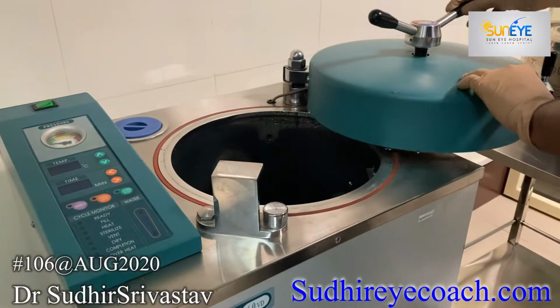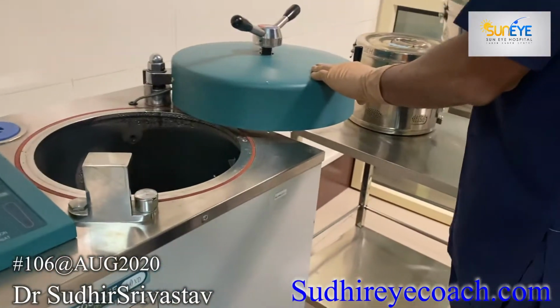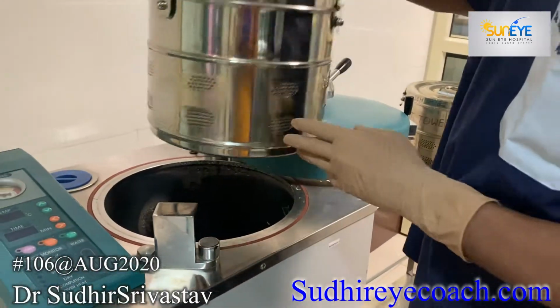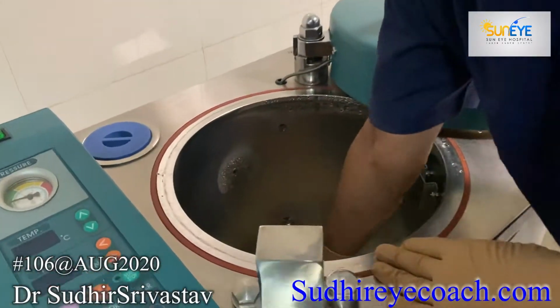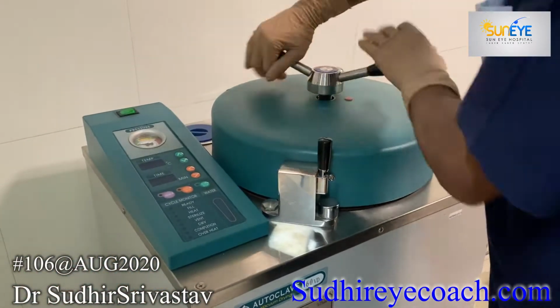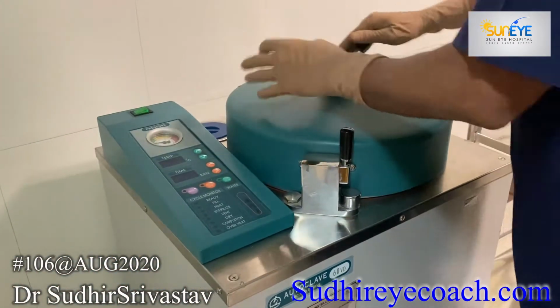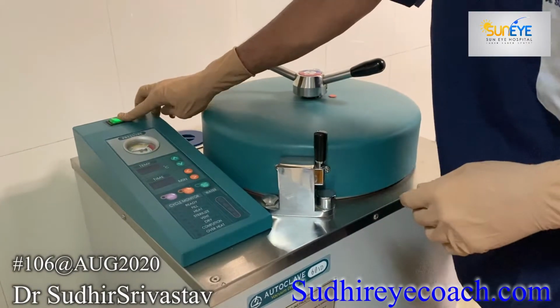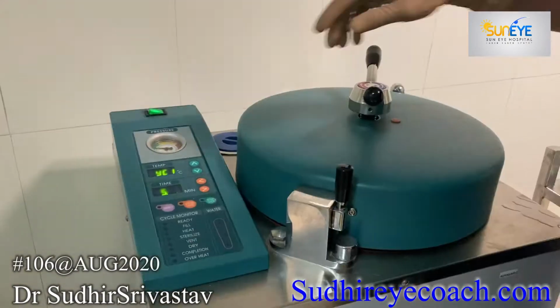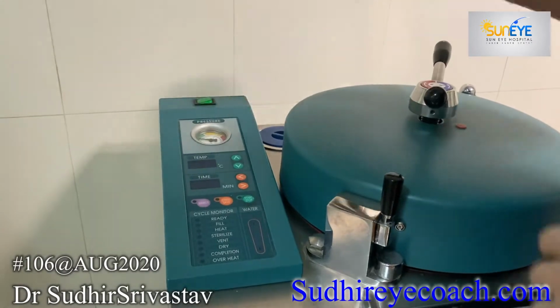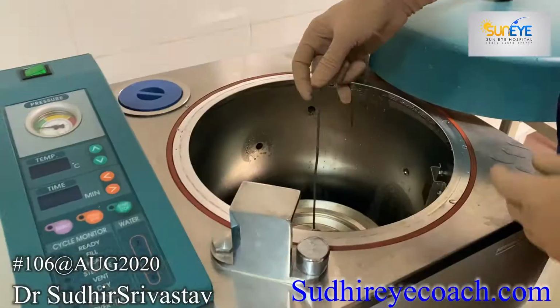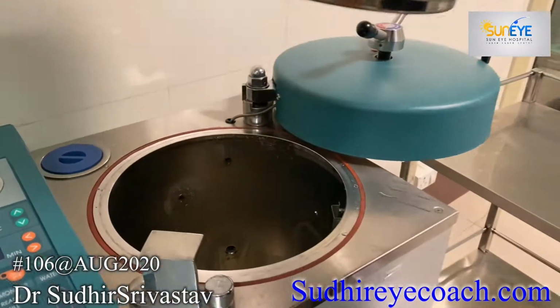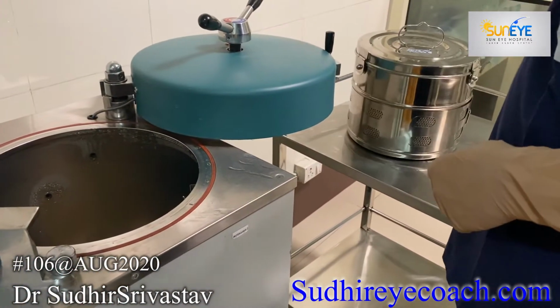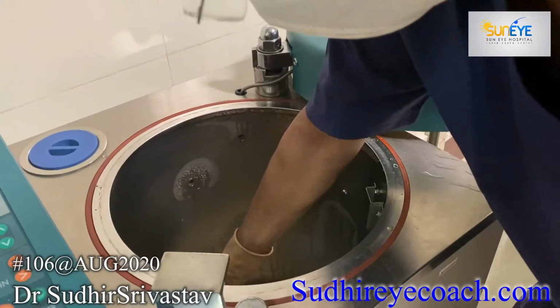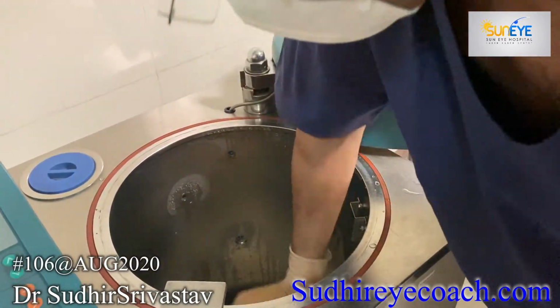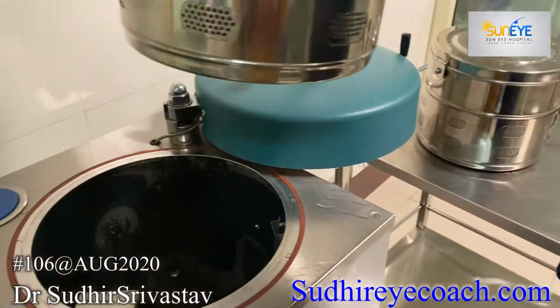Prepare the autoclave. Do the Bowie-Dick test to check the vacuum efficiency of the equipment every day before sterilization. How we do the Bowie-Dick test can be seen in my previous videos. Switch on the autoclave. Wait for completion of the cycles. It may take an hour. After the whole process, open the autoclave and remove the surgical drums for inspection. The air quality of the autoclaving room must be clear and dust-free.